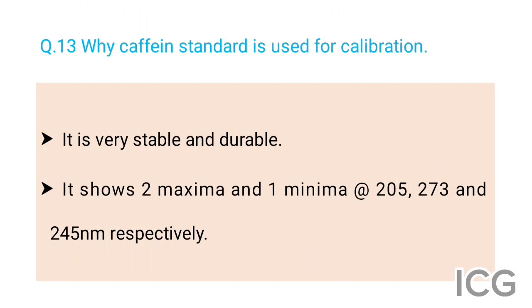The next question is: why is caffeine standard used for calibration? The answer is there are two reasons. Number one, it is very stable and durable. Number two, it shows two maxima and one minima at 205 nm, 273 nm, and 245 nm respectively.